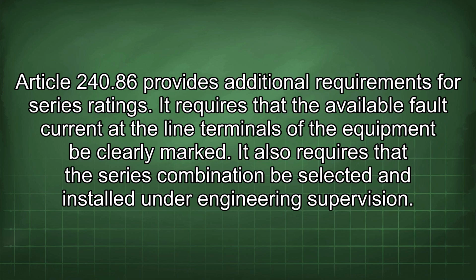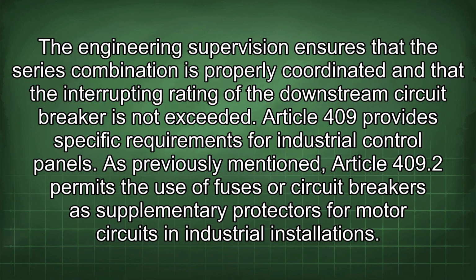It requires that the available fault current at the line terminals of the equipment be clearly marked. It also requires that the series combination be selected and installed under engineering supervision. The engineering supervision ensures that the series combination is properly coordinated and that the interrupting rating of the downstream circuit breaker is not exceeded. Article 409 provides specific requirements for industrial control panels.